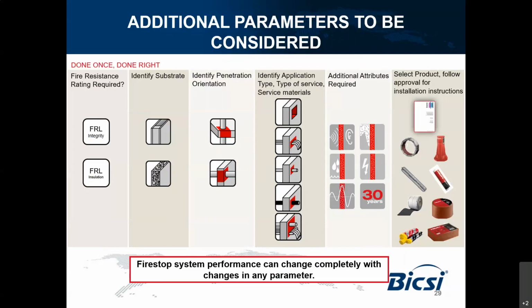Then we need to understand the orientation and the size—pay attention to the size of the opening. In a lot of cases, people think, oh, I've got a 16mm cable, let's do an 18mm hole, perfect. But later they find out, unfortunately, the tested system requires a bigger opening, because my system uses inch-dimension mastic in the apertures, in the annular gaps. So the opening ends up not being correct, and they need to do it again.